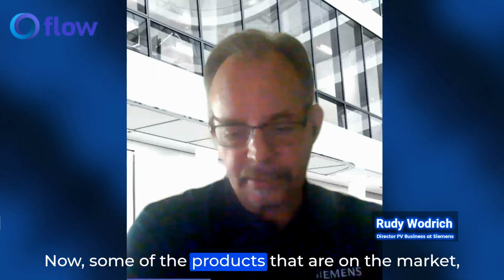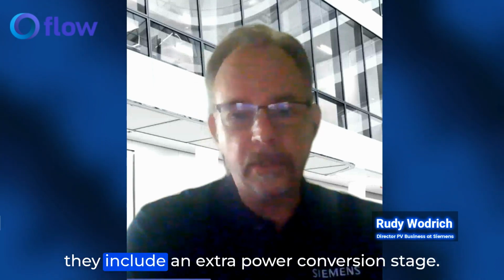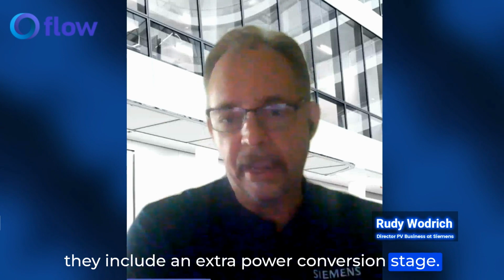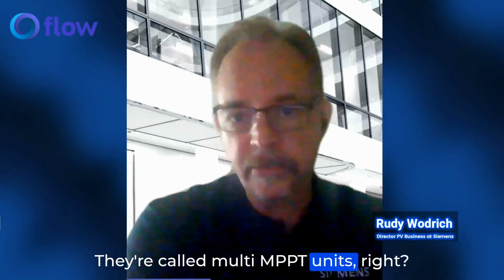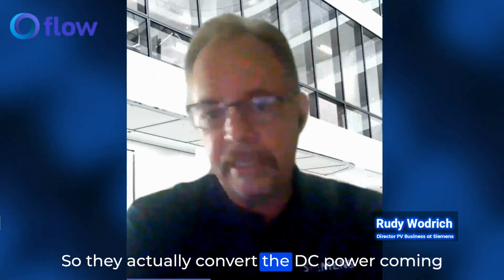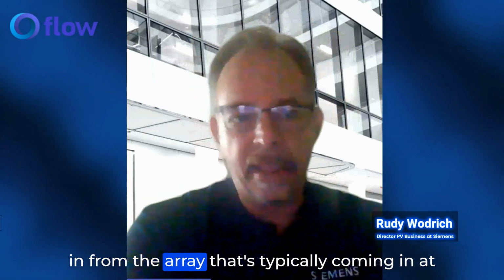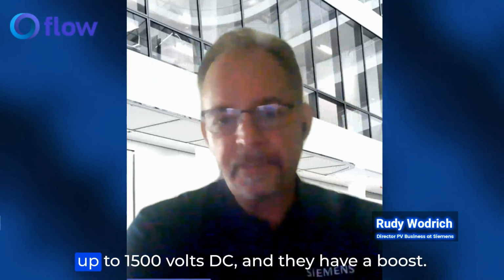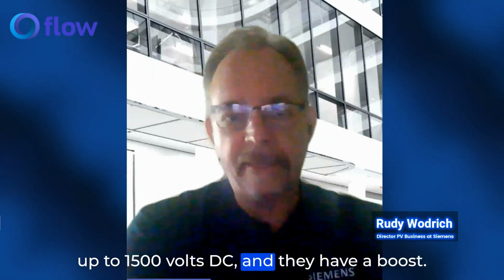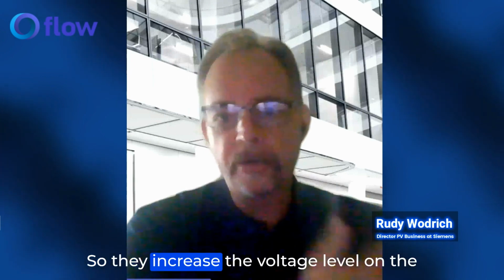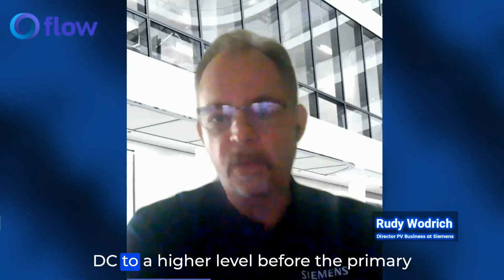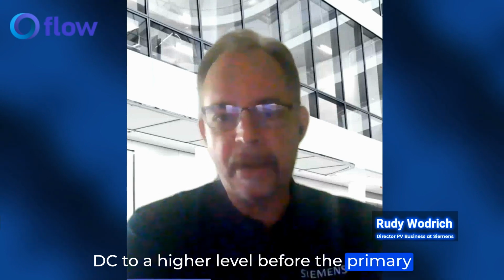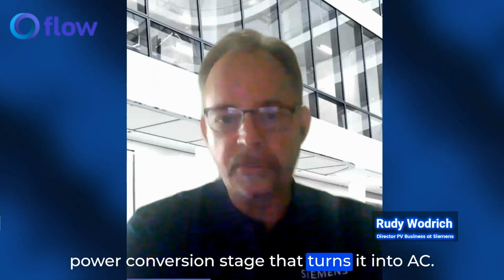Now, some products on the market include an extra power conversion stage—they're called multi-MPPT units. They actually convert the DC power coming in from the array, typically up to 1500 volts DC, and boost it, increasing the voltage level on the DC to a higher level before the primary power conversion stage that turns it into AC.